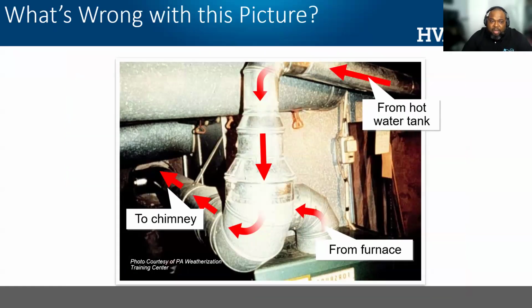This is another bad situation. Looking at this, we see we have the exhaust from the hot water heater traveling downhill. Those exhaust gases are going to spill from this piece of equipment. If I have both the appliance making carbon monoxide and it spilling into the house, I can have an event. So once we test, to hammer it home, we have to inspect.